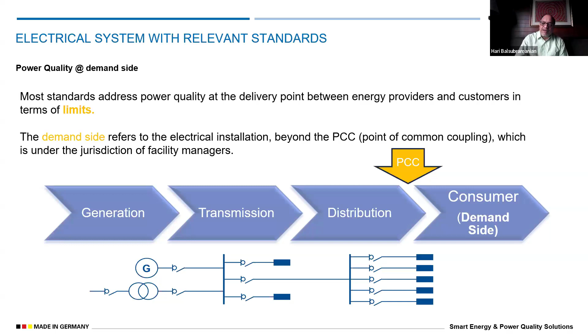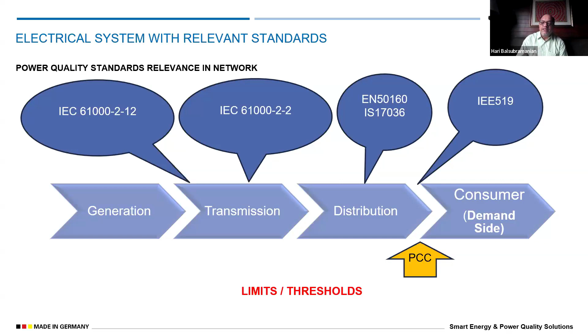What standards are relevant in the network? We have 61000-2-2 for transmission, EN50160 and IS 17036 for distribution systems, and IEEE 519 for consumers, which clearly states voltage is the responsibility of distribution companies and current harmonics is the responsibility of consumers. These standards give limits for individual harmonics, TDD, THD—everything specified—and we must work within those thresholds. This leads to demand side power quality management, now called IEC TS 63191.